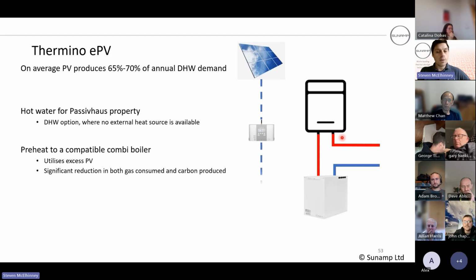So one thing to remember though is, in this configuration, check with the boiler manufacturer what the maximum inlet temperature is on the cold water inlet, because some manufacturers will only allow a 15-degree maximum inlet temperature. And obviously we're going to exceed that, so you'd have to blend it down. But I think with the Worcester 8000s nowadays, you can have a preheat quite happily. Was it the Alphas as well? So obviously they're catching on to that idea.